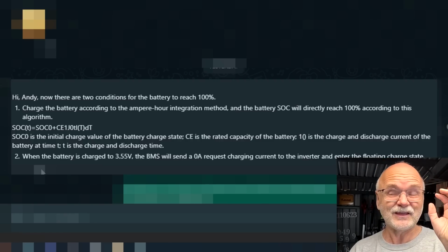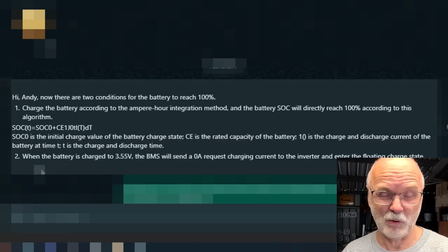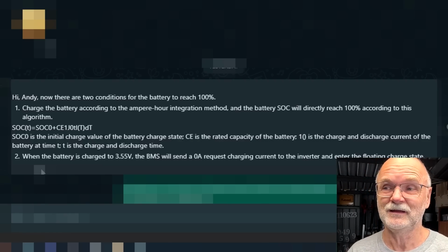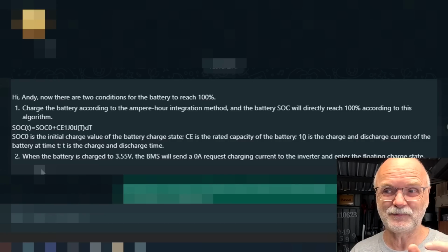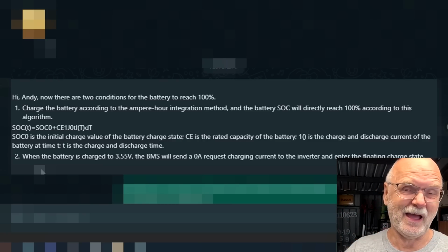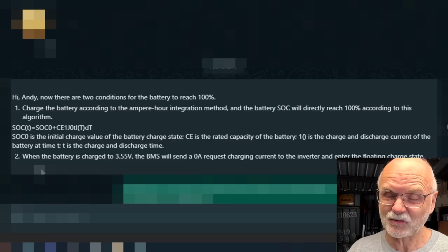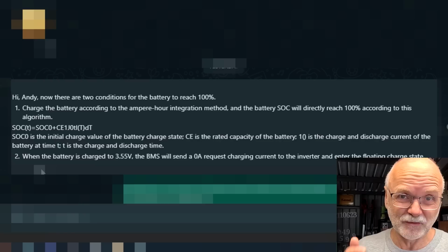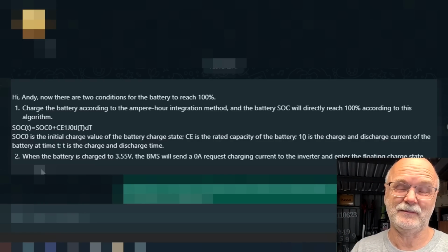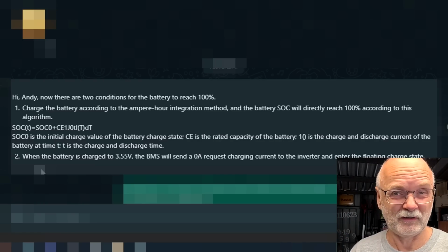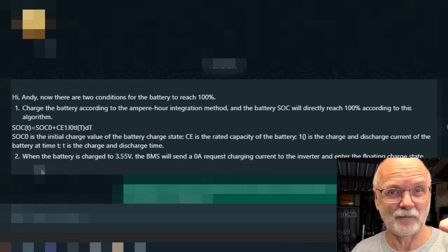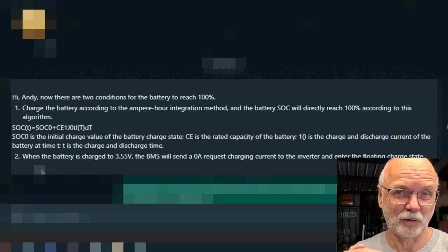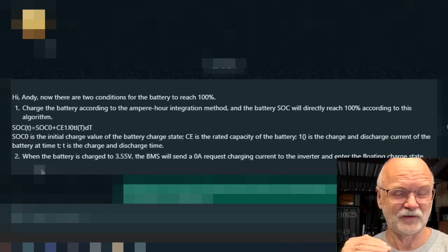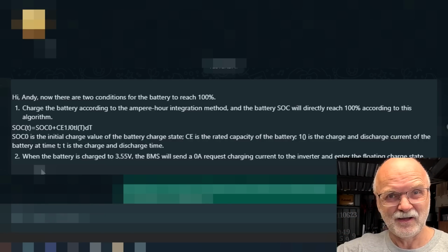I think it will only keep the voltage at 3.55 volts and float the battery there, which is far too high. This is why we have a real float mode now in the JK BMS. We charge to 3.45 volts, absorb for half an hour, then lower the voltage to 3.35 volts per cell and keep it there forever.